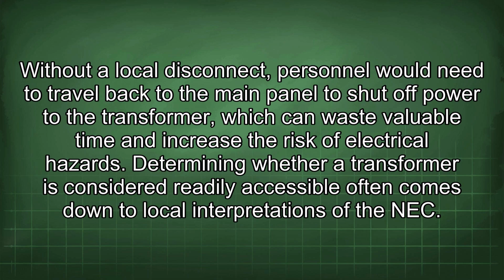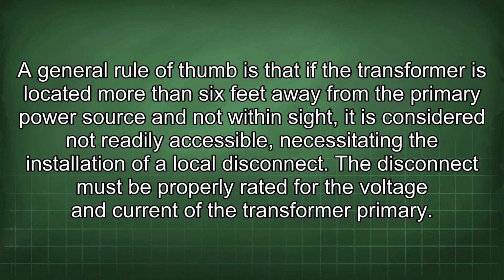Determining whether a transformer is considered readily accessible often comes down to local interpretations of the NEC. A general rule of thumb is that if the transformer is located more than 6 feet away from the primary power source and not within sight, it is considered not readily accessible, necessitating the installation of a local disconnect.